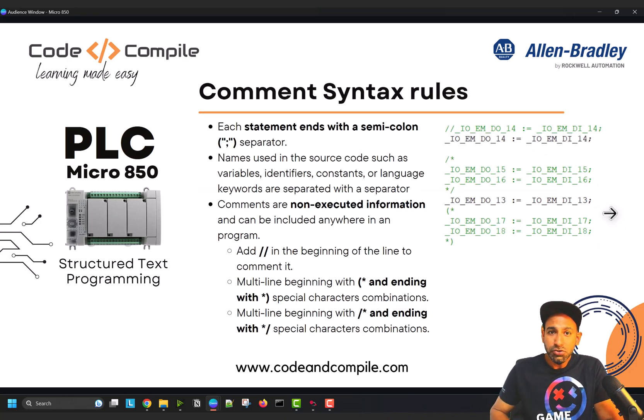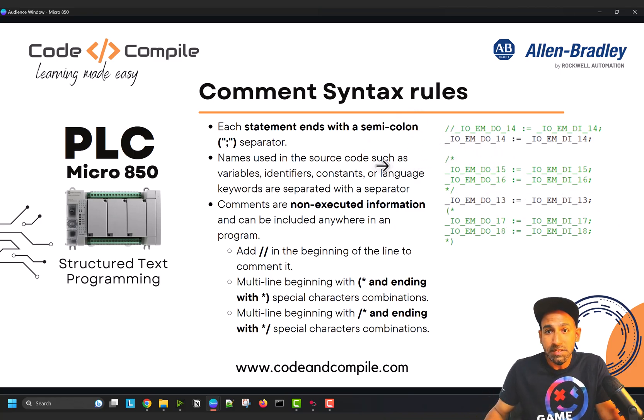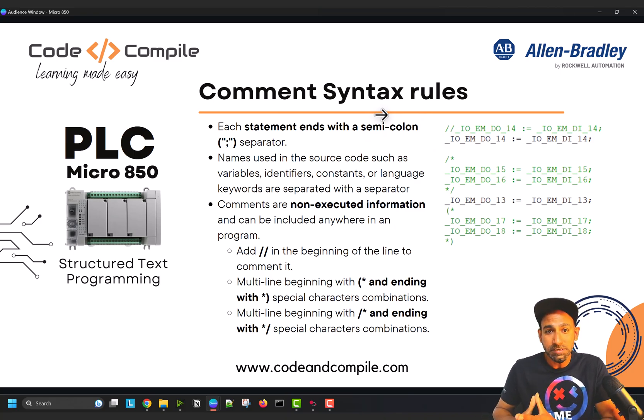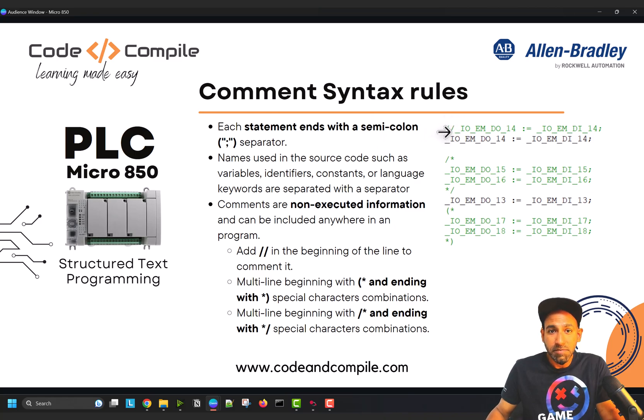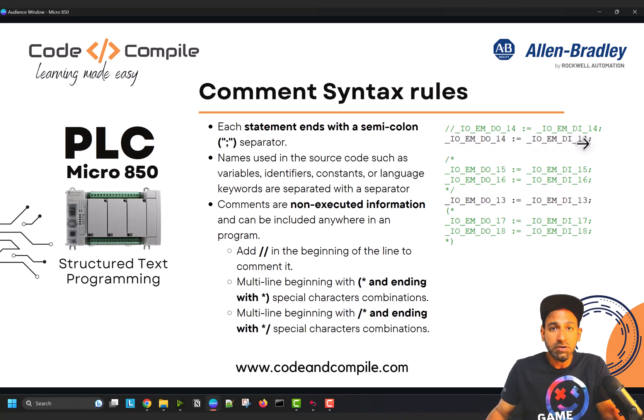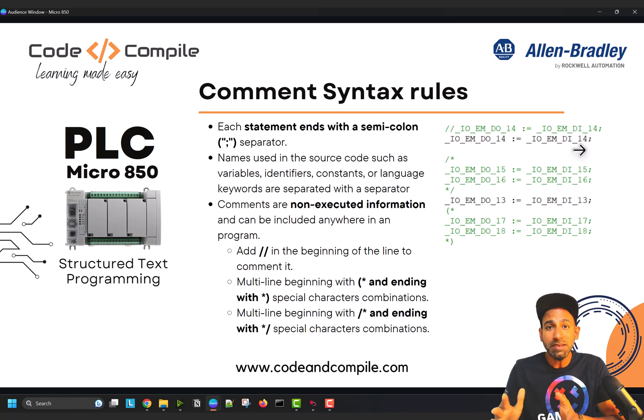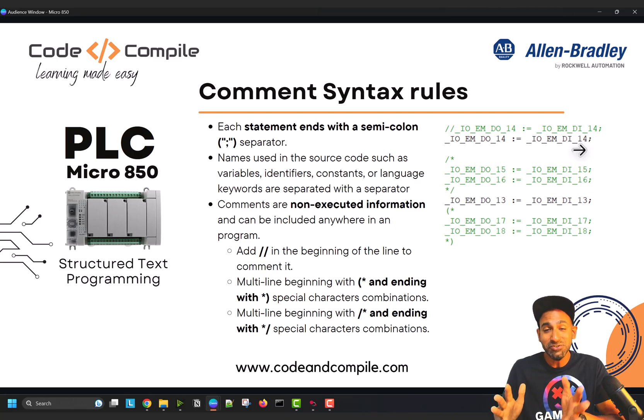How do you write the language? Here is an example of how you write comments — the first syntax rule. To write a comment, you put two slashes, as you can see in the image. Each statement ends with a semicolon. This is a very important rule when writing Structured Text — if you don't put a semicolon, you will get an error. Sometimes it's just this tiny error that takes many minutes or hours to find, so make sure you put a semicolon.